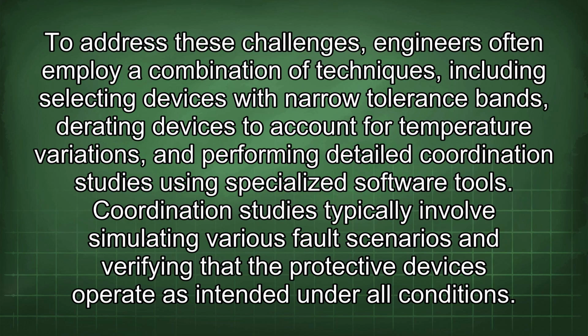To address these challenges, engineers often employ a combination of techniques, including selecting devices with narrow tolerance bands, derating devices to account for temperature variations, and performing detailed coordination studies using specialized software tools. Coordination studies typically involve simulating various fault scenarios and verifying that the protective devices operate as intended under all conditions.